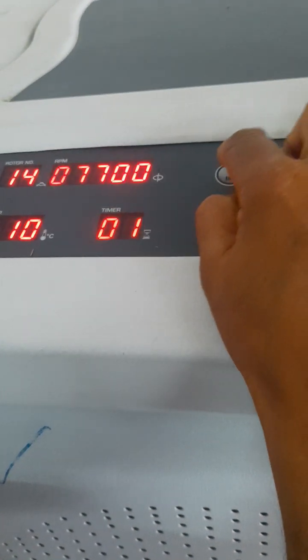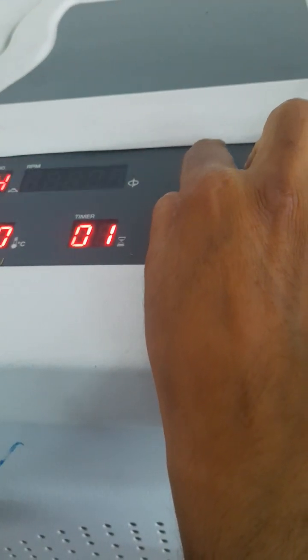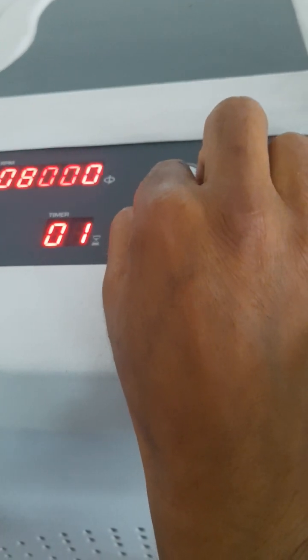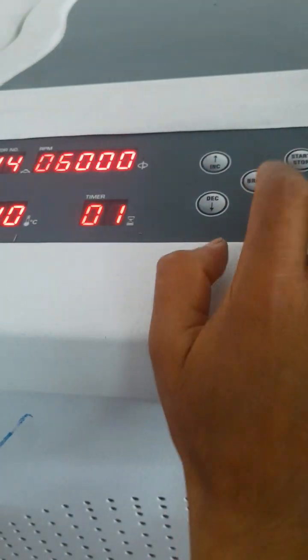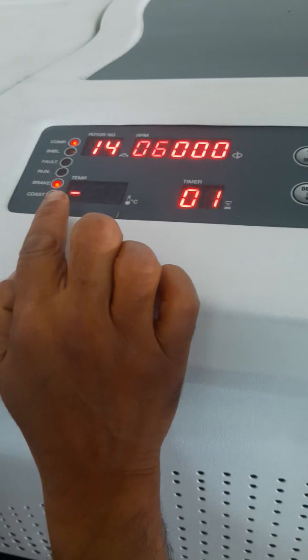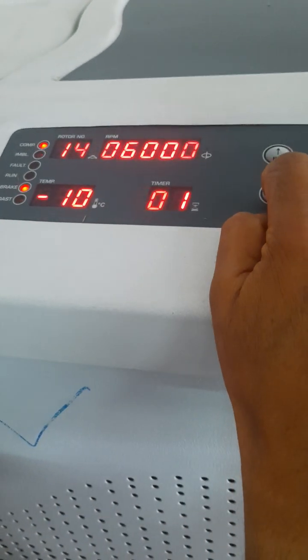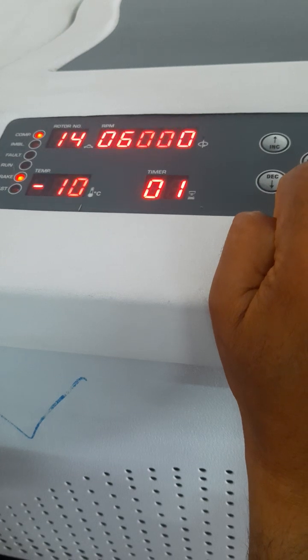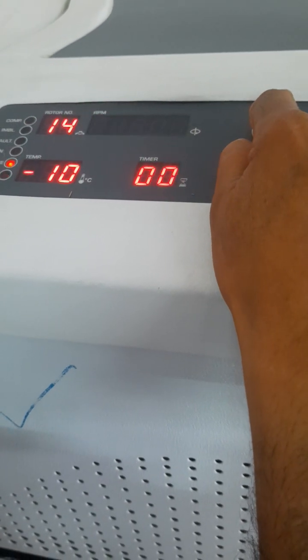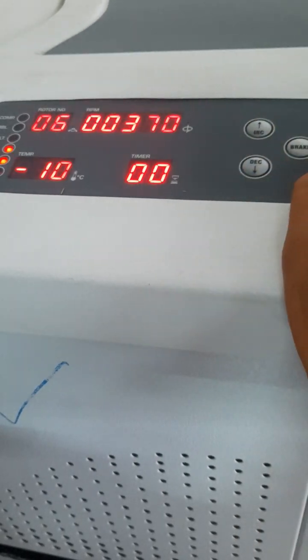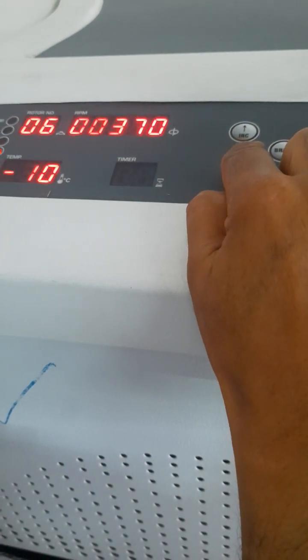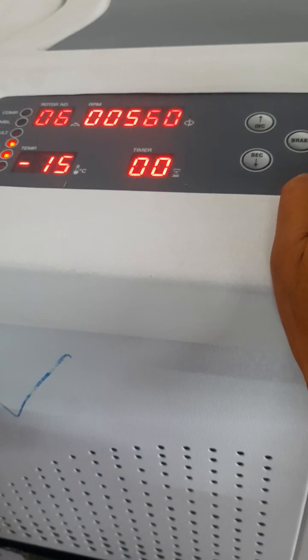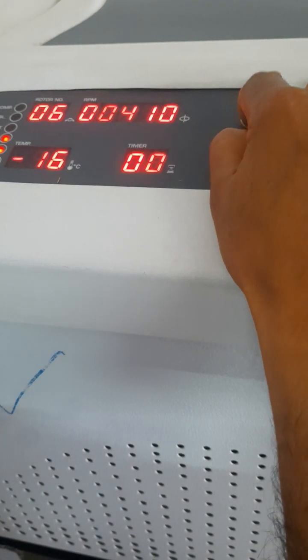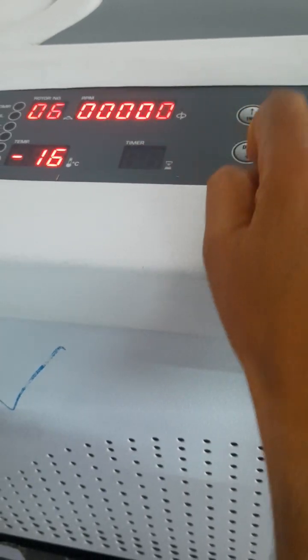Now I will go to the rotations per minute. I will set these at 6,000 rotations per minute. So I have set 6,000 rotations per minute. Now I will go to this section, that is the temperature setup. For example, we have analysis of any blood sample. I can set the temperature at this temperature. This is the timer. At timer we will set the time at how many minutes? 5 minutes, I think. That is 5 minutes.